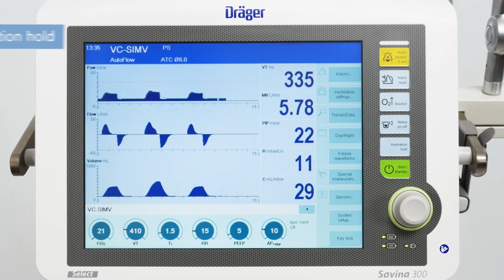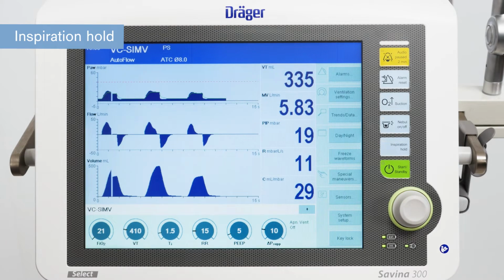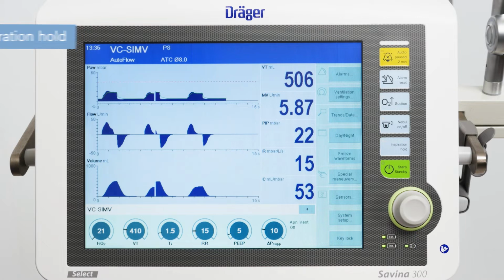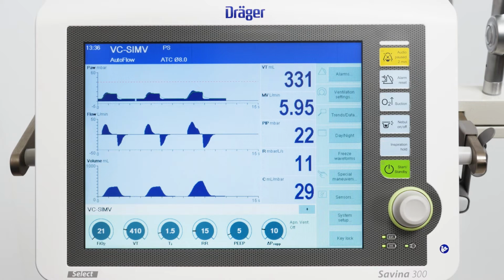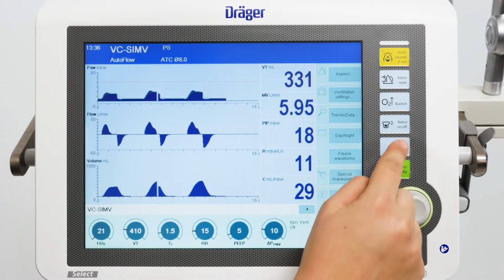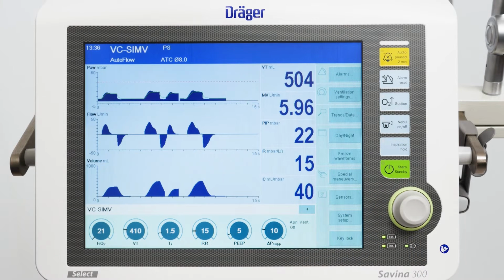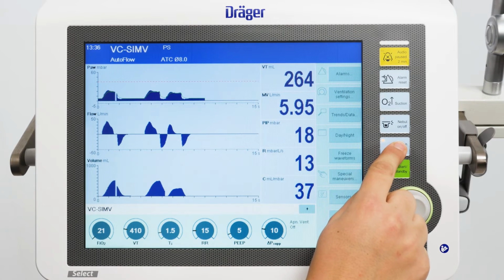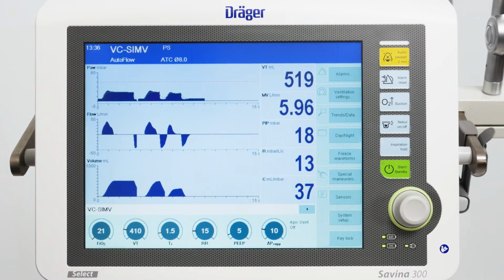The inspiration hold maneuver can be activated in all ventilation modes. Between two automatically delivered breaths, a breath can be manually started and held, or regardless of the start time, an automatically delivered breath can be prolonged. For triggering manual inspiration, briefly press the inspiration hold key. For extending manual inspiration, press the inspiration hold key and hold for the desired inspiratory time.